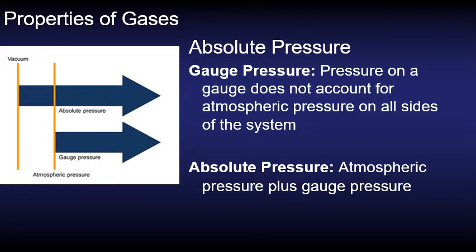So what do we mean by absolute pressure? First of all let's look at gauge pressure. If we look at a pneumatic system we will usually see a gauge and the gauge will show us the gauge pressure which doesn't account for the atmospheric pressure that's on all sides of the system. So we're surrounded at any given time by a certain amount of air pressure. In order to calculate the absolute pressure we need to add in that atmospheric pressure plus the gauge pressure.